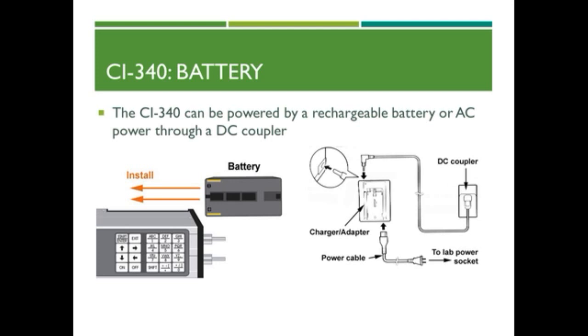When the battery voltage is below 5.6 volts, the message "Low battery" will appear on the screen. This indication signals an approximate 5 minutes of use remaining before the instrument shuts down. The battery eliminator can be used to power the CI-340 from the wall socket for long-term monitoring or for use when the batteries are not charged. The battery charger will only charge the battery or power the device. It will not do both at once.